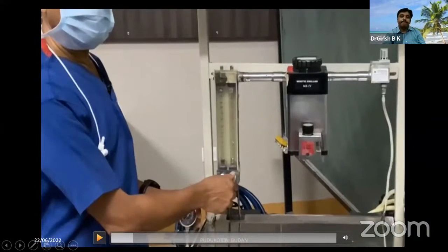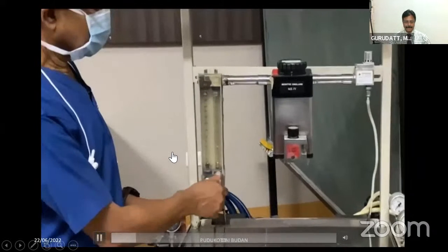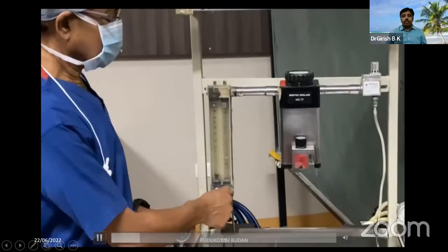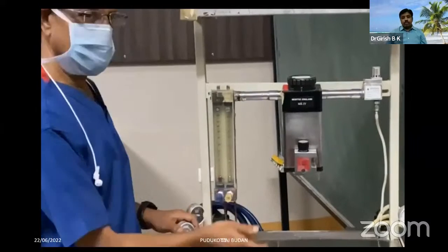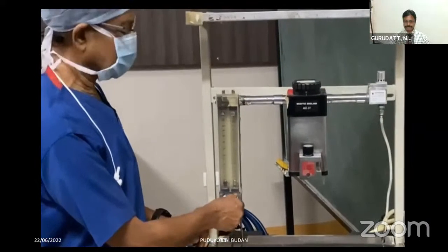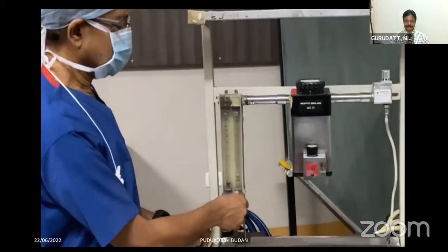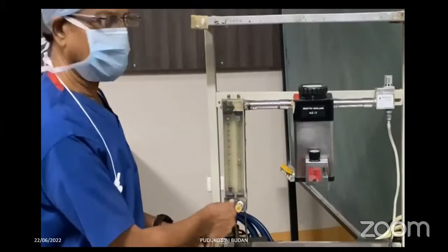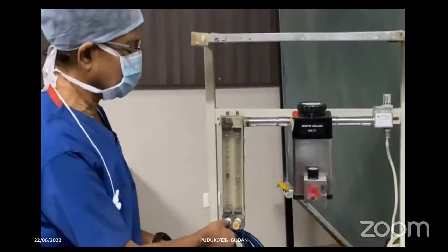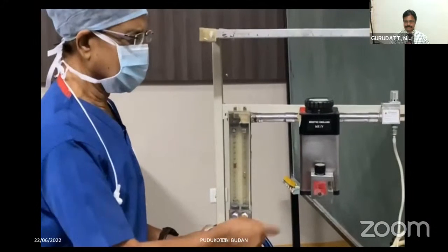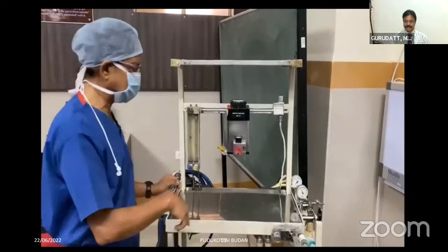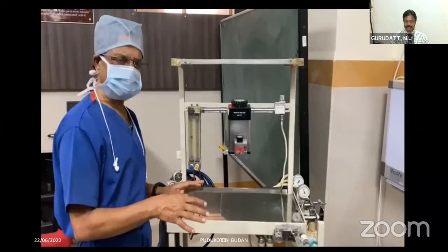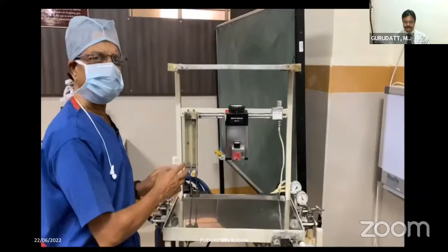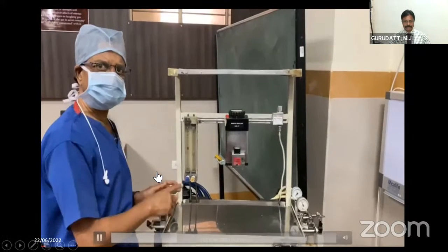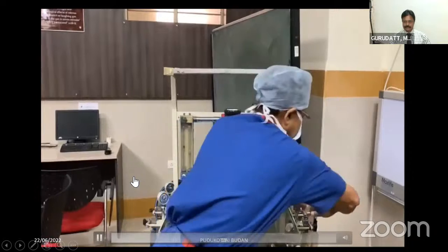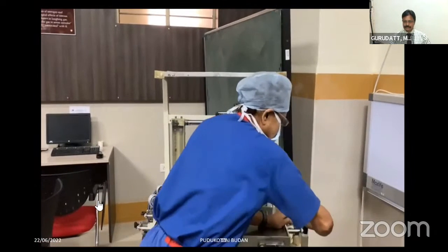Now, okay. What I am doing is I am opening oxygen. So oxygen flow is there, oxygen pressure is there through the nitrous oxide pressure regulator because I have opened the oxygen cylinder. Now I have kept both oxygen and nitrous oxide. You see, I can open nitrous oxide now. So now I will close the oxygen cylinder. That means there won't be any pressure of oxygen to open up nitrous oxide, so the nitrous oxide also should fall down. So I am just closing down the cylinder of oxygen.